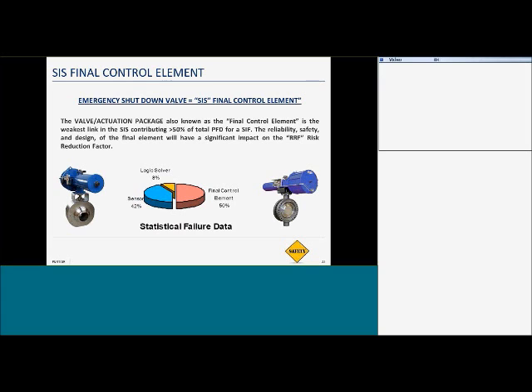Really, sensors are electronic pieces of equipment, logic solvers as well, with a very highly known probability of failure on demand. When we look at the final control element, we're now talking about a lot of different variables that can be put into play. Probably most importantly would be the fact that this is a device that's mechanical and it's in line with the media. So if we think of this in terms of applications out there like sulfur vapor recovery, where it's very sticky, we can get all kinds of valve failure caused just by the application of the process as well as the application of the valve. So we've got a lot more reliability issues and concerns with the final control element. So this is really what brings us to the table in SIS and why it's such a big focus for us.